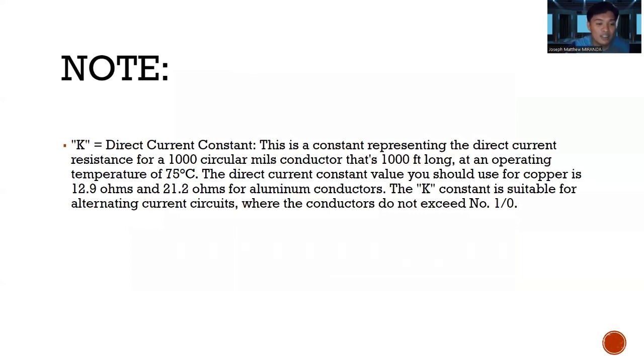So note, K is equals to direct current constant. This is a constant representing the direct current resistance for a 1,000 circular mil conductor that's 1,000 feet long at an operating temperature of 75 degrees Celsius. The direct current constant value you should use for copper is 12.9 ohms and 21.2 ohms for aluminum conductors.